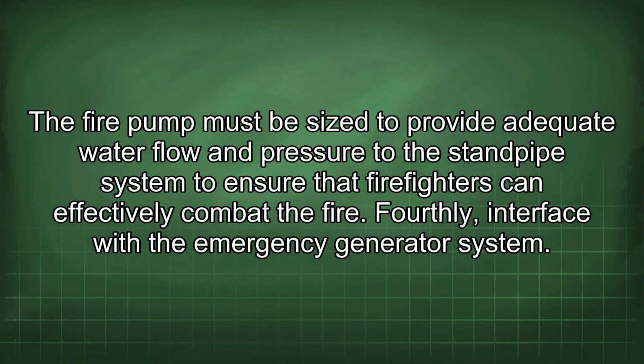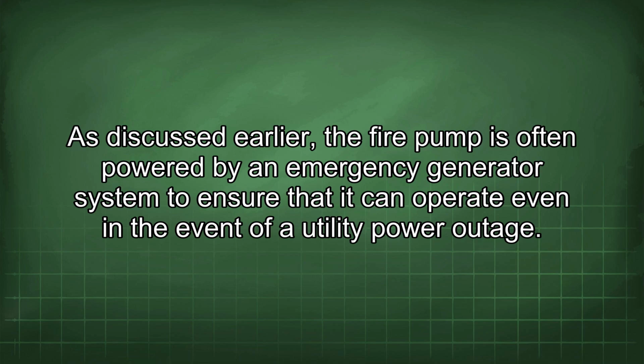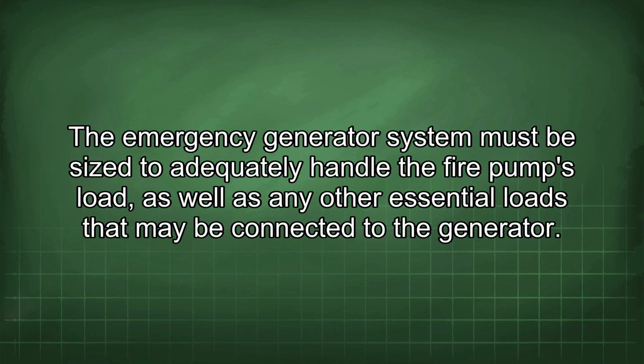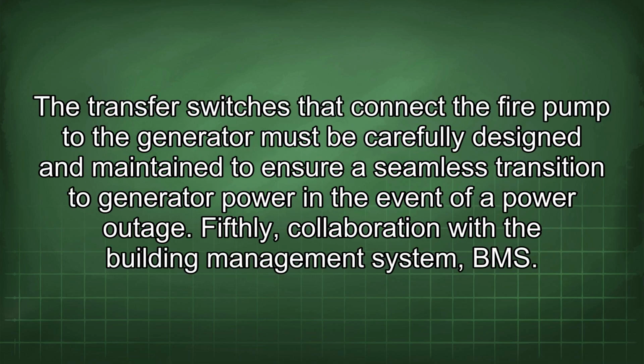Fourthly, interface with the emergency generator system. As discussed earlier, the fire pump is often powered by an emergency generator system to ensure that it can operate even in the event of a utility power outage. The emergency generator system must be sized to adequately handle the fire pump's load, as well as any other essential loads that may be connected to the generator. The transfer switches that connect the fire pump to the generator must be carefully designed and maintained to ensure a seamless transition to generator power in the event of a power outage.